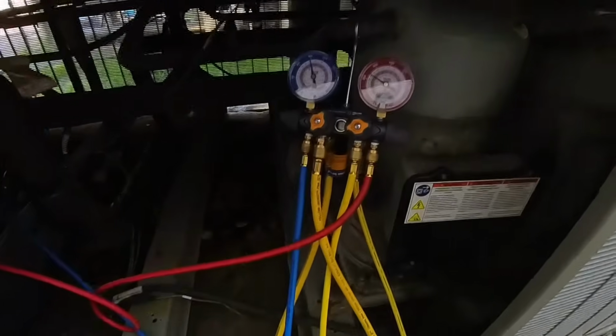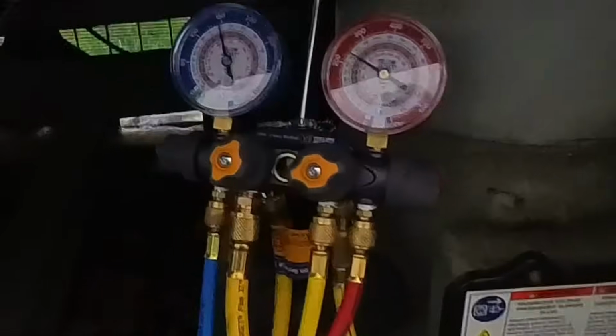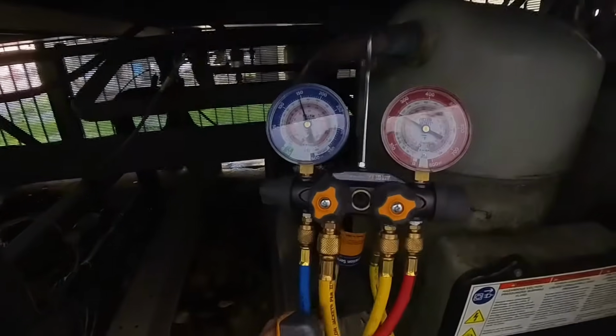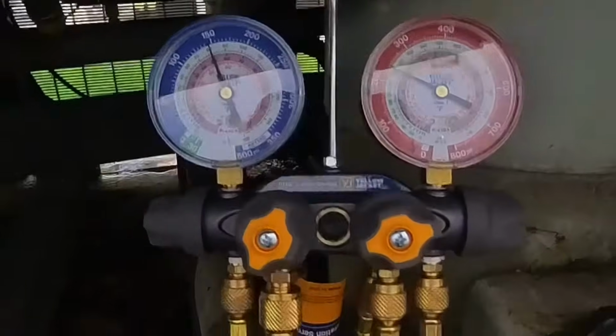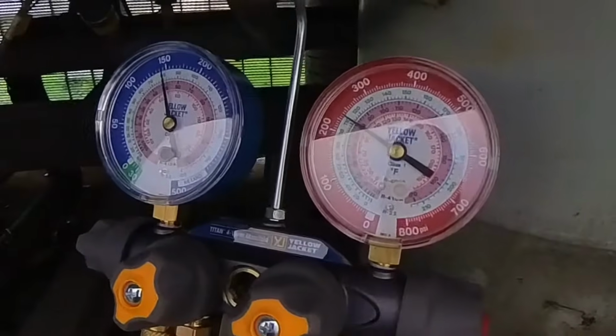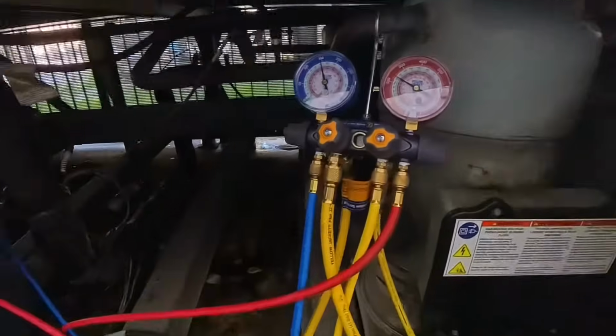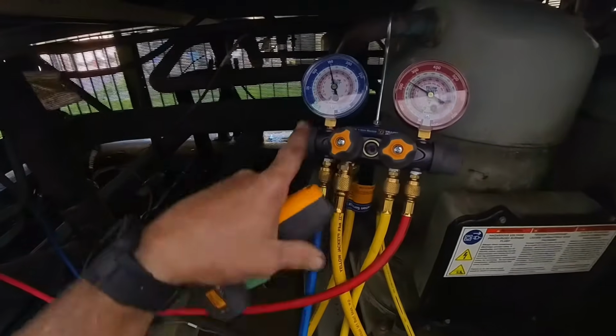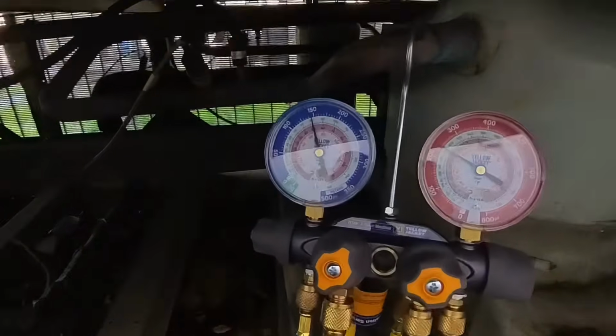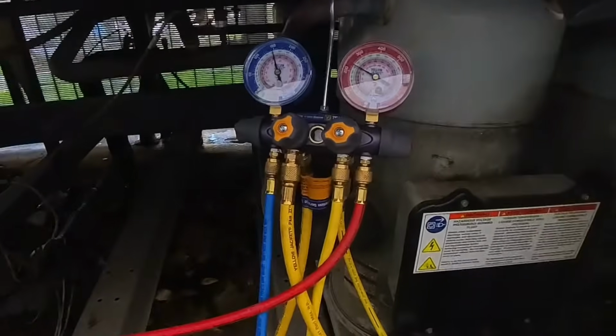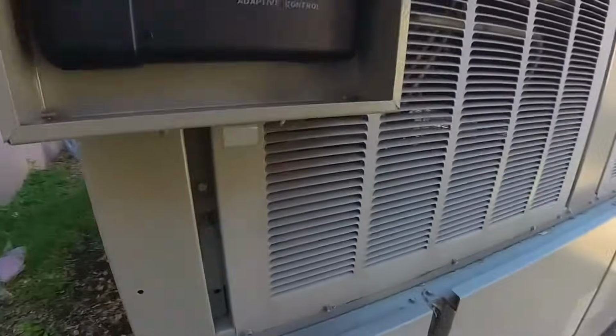Alright, so I got my gauges hooked up here to circuit 2. And our standing pressure, we got 145 and roughly about 235, 240 on the high side. Our saturated temperature works out to be about 51-ish. And this was saying circuit 1 saturated suction temp was 51.6. Our suction temperature was 85.5, so let's measure that.